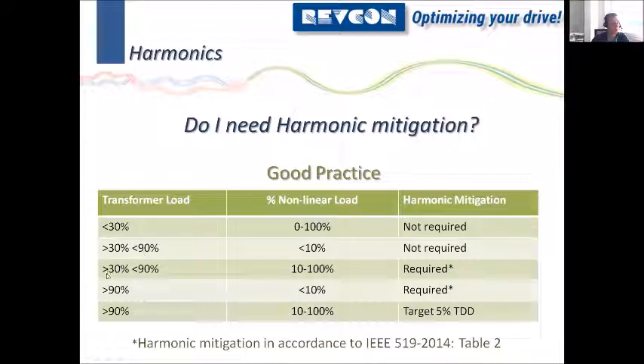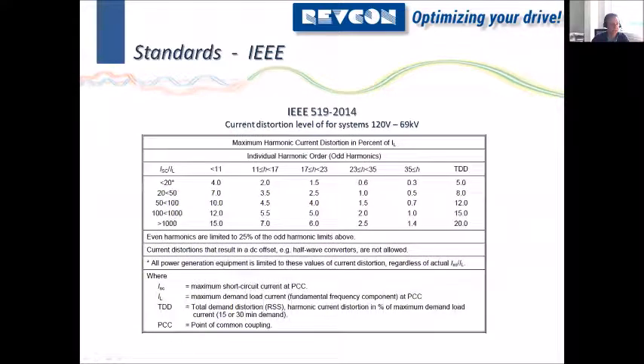If your load is in the same area, 30 to 90%, but you have nonlinear load of 10 to 100%, you should use the table of the IEEE 519/2014 and check what kind of harmonic mitigation you will need. It's really essential to do the calculations on this table, because if we look here, if you only have 10% load, you might only need a filter on maybe one drive or two drives. But if you always assume this worst case, if you don't get any values, you could always say, okay, I will make it worst case and I will assume 5% TDD.